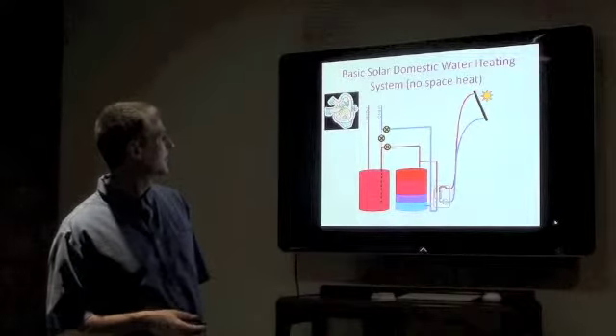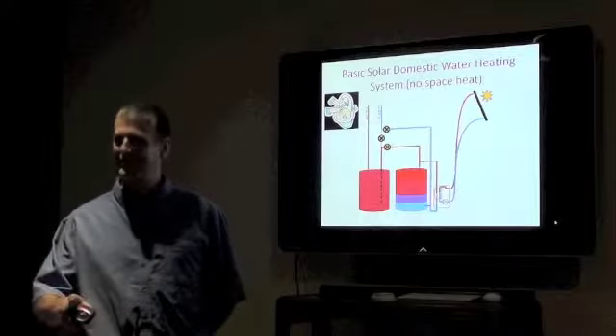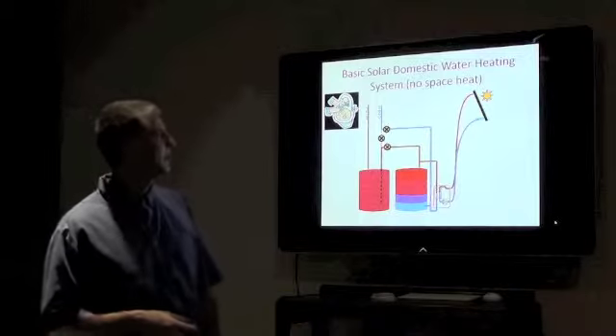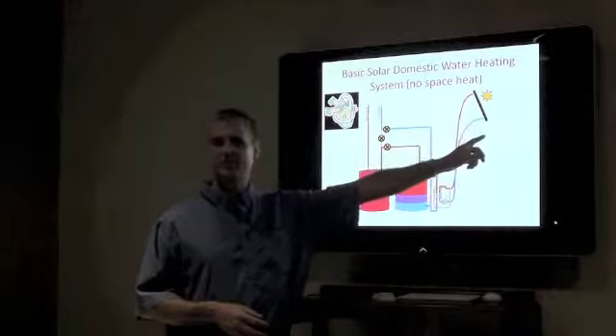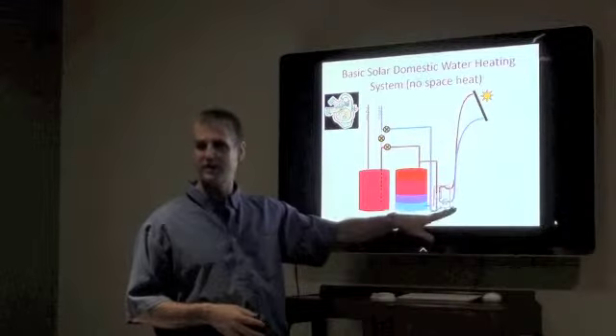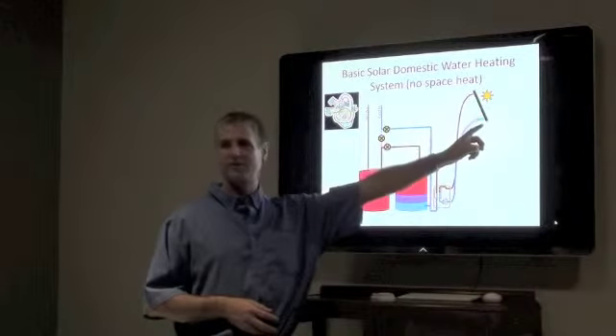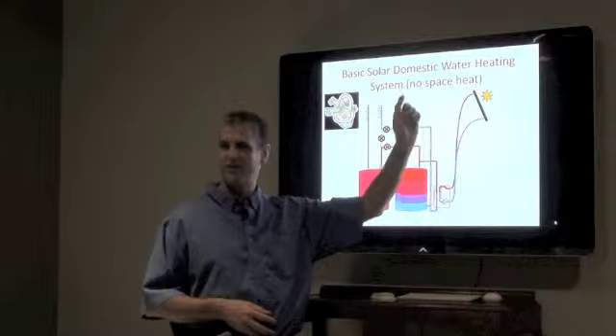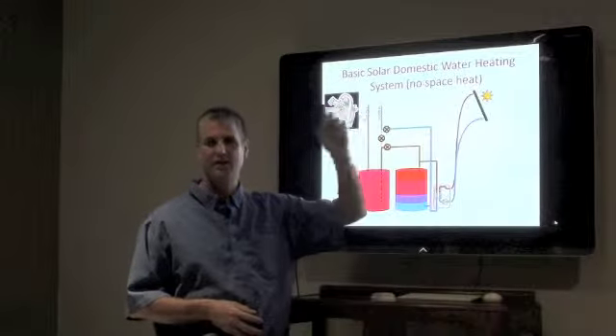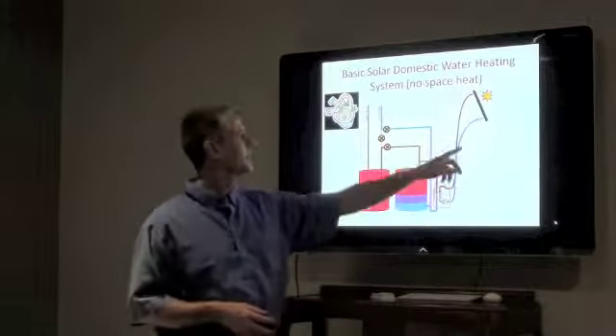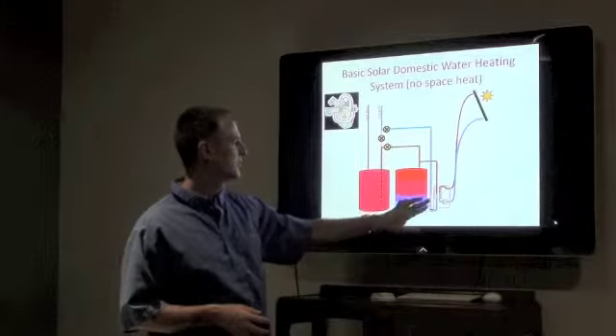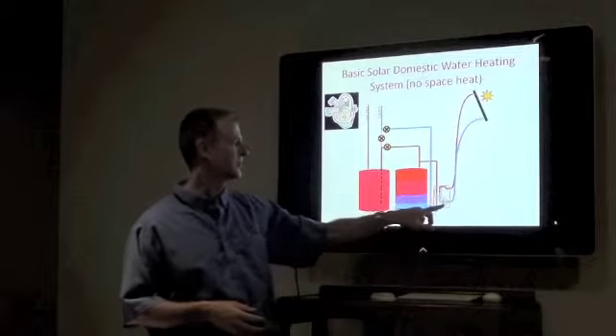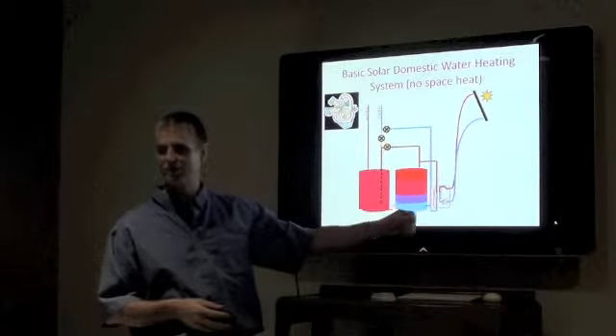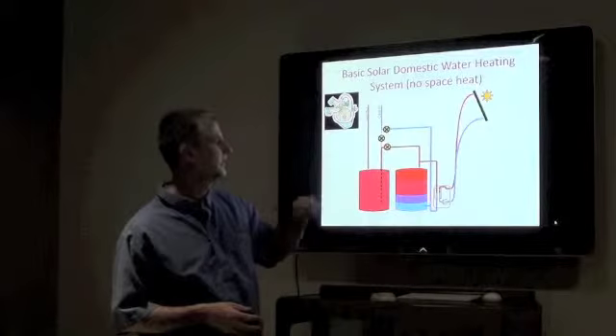So this is our basic install for domestic water heating, like would come out of your tap. On this system, which has Enerworks as a manufacturer, there are from 1 to 4 of these panels. On the picture I showed of my house, there was 1. On this house, there are 3. Glycol lines run to what's called an energy pack, which is basically a pump, heat exchanger, and controller. There's a couple other components in there.